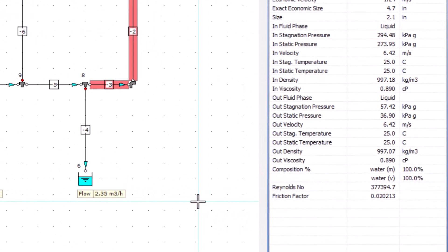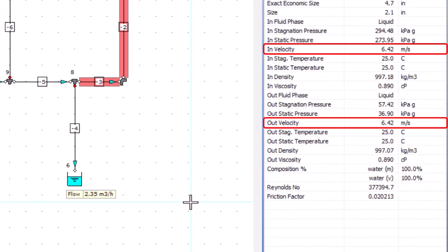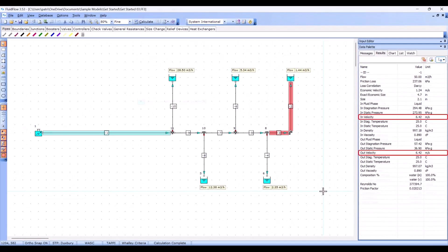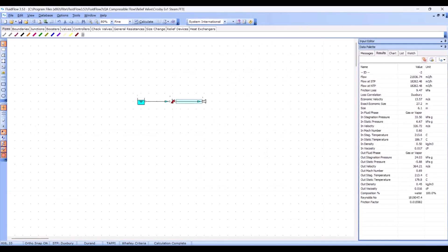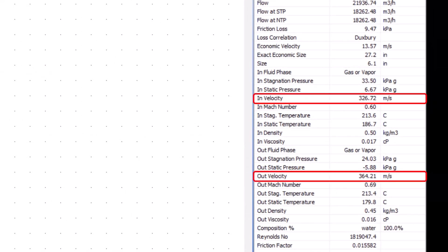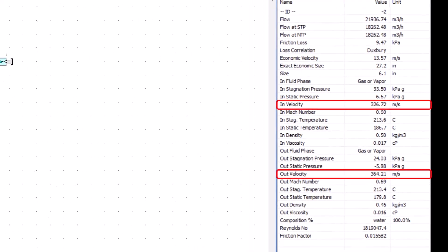We can see there's no velocity change because we're using a liquid. In a gas system like this one, however, you can see that the gas accelerates along a pipe. Fluid flow uses a complex algorithm for solving gas networks. It splits each element into sub-elements of varying lengths based on the rate of change of density in the pipe. This ensures that we get more calculations happening when the changes are taking place more quickly.